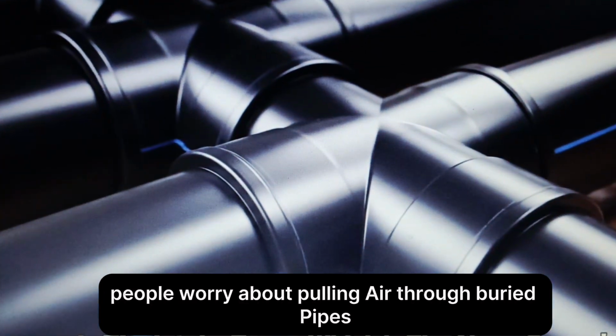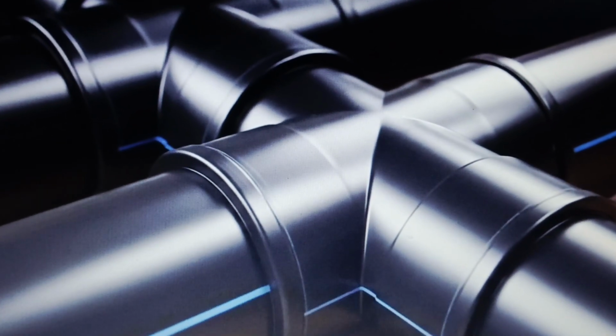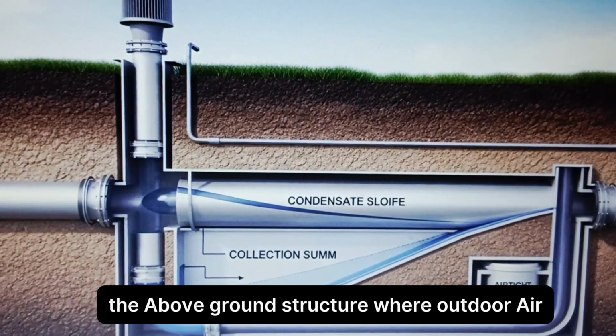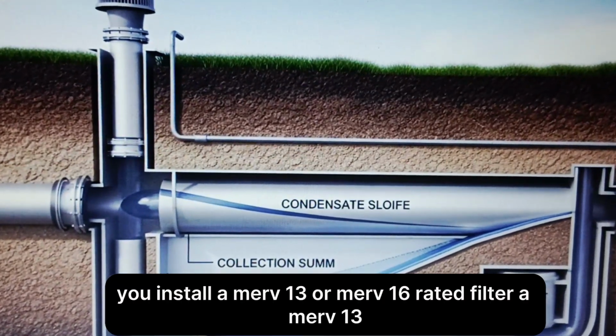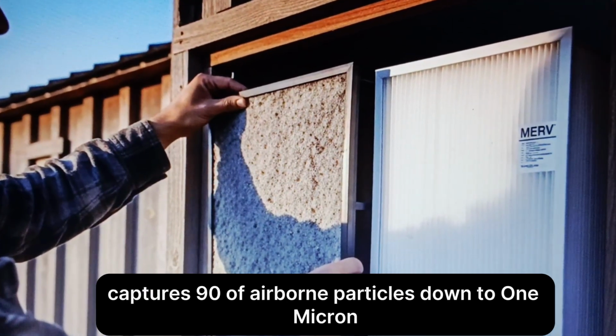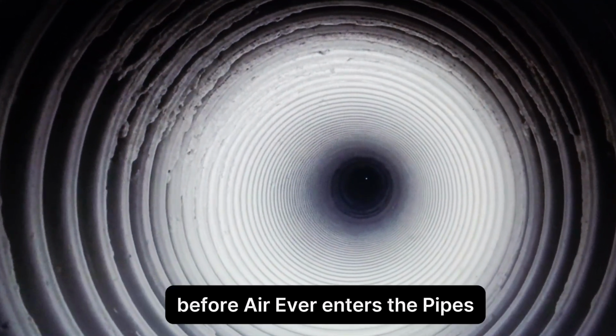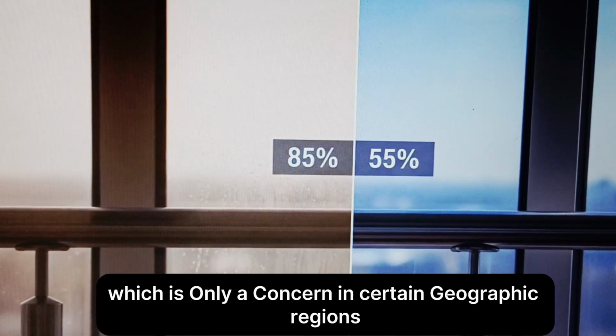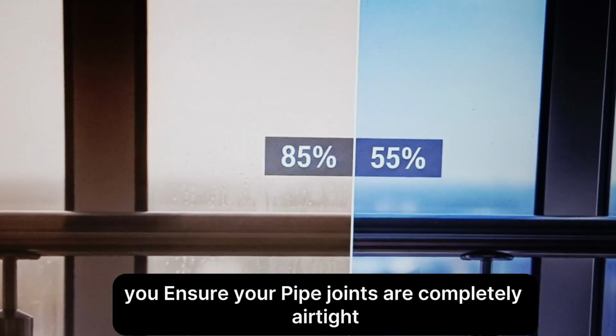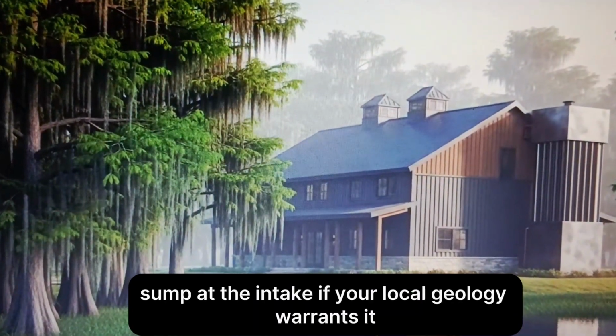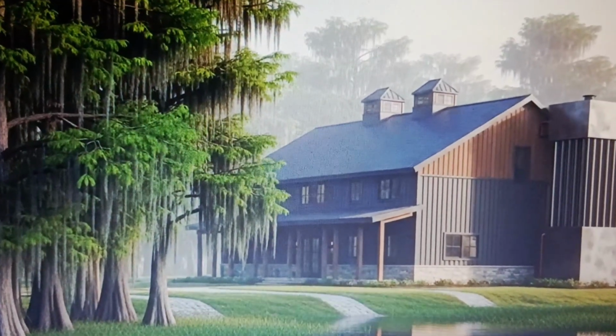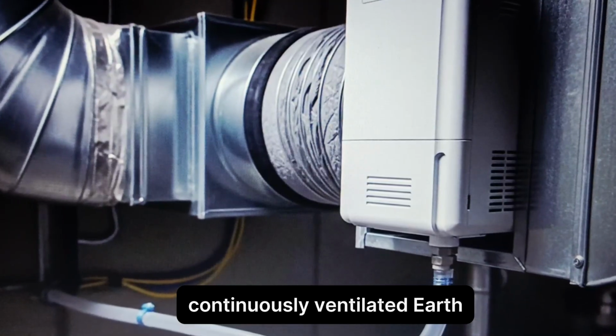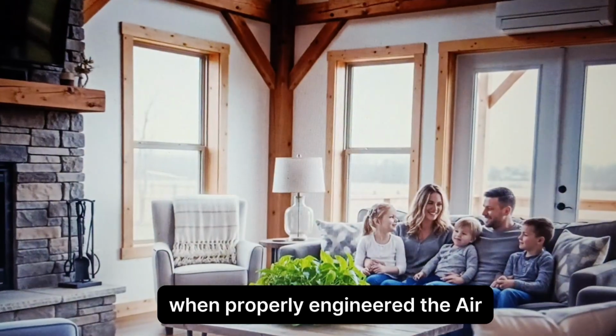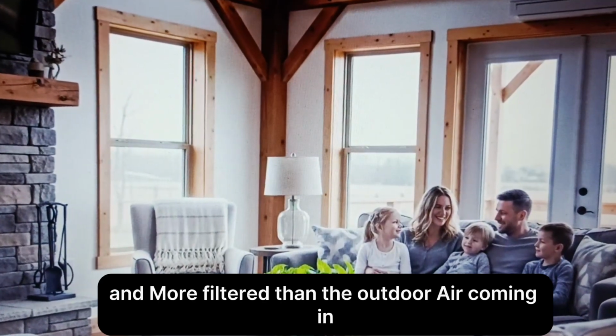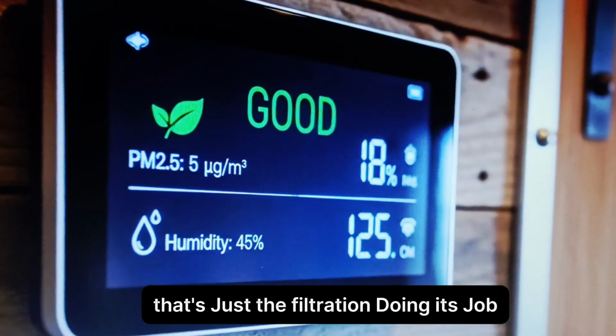People worry about pulling air through buried pipes, radon, soil gases, contamination. Here's how that's handled. At the intake tower, the above-ground structure where outdoor air first enters the system, you install a MERV 13 or MERV 16 rated filter. A MERV 13 captures 90% of airborne particles down to 1 micron, pollen, dust, mold spores, most bacteria, before air ever enters the pipes. For radon specifically, which is only a concern in certain geographic regions, you ensure your pipe joints are completely airtight and install a radon sump at the intake if your local geology warrants it. Radon is heavier than air and accumulates in enclosed spaces, not in continuously ventilated earth tubes with constant airflow. When properly engineered, the air coming out of your earth tubes is actually cleaner and more filtered than the outdoor air coming in. That's not a selling point. That's just the filtration doing its job.